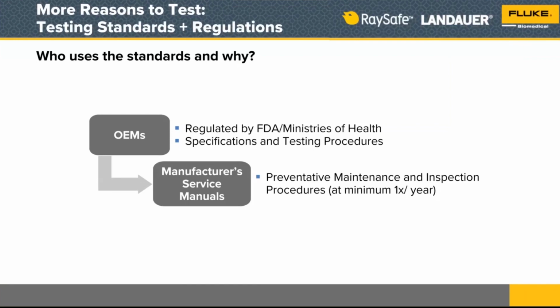So the manufacturer's service manual procedure will be a result of those tests. They may or may not include all of the tests exactly the way that they would have done them from the standard, but they will be based on the standard test methodology and the testing limits from the standard. And that's how they get to you, is through those service manuals.